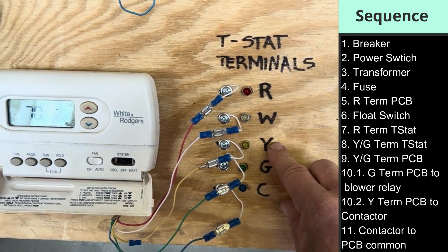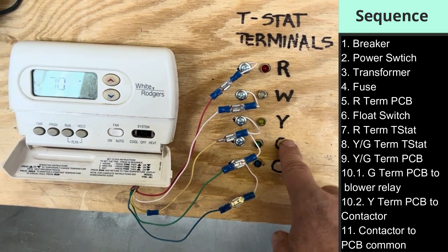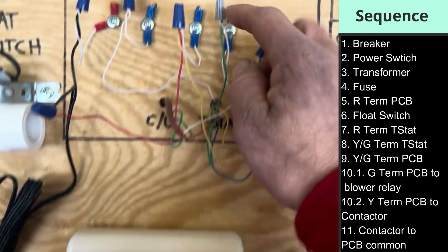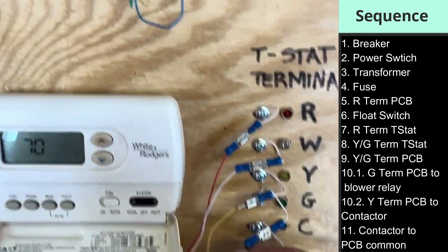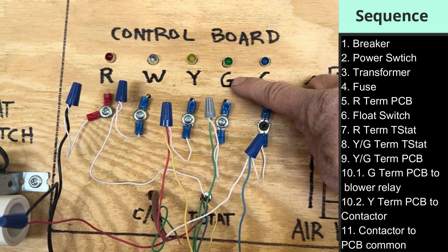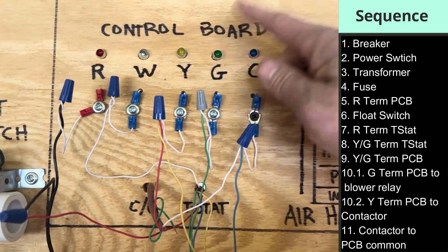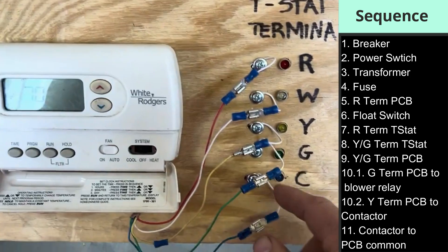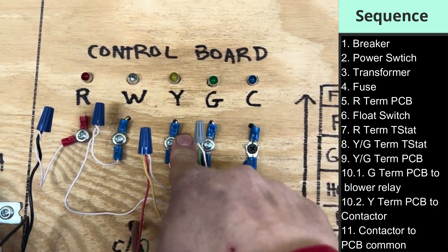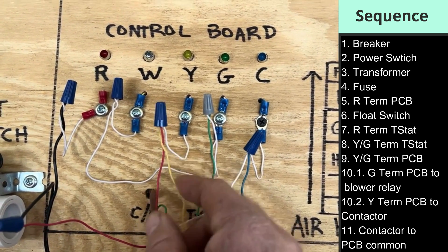In cooling mode, the thermostat makes connections between the R terminal and sends 24 volts to our Y terminal, and also sends 24 volts from R to G — Y is for cooling, G is for our blower motor. Both of these terminals get powered at the same time in cooling mode. The Y goes back on a yellow wire to the control board Y terminal, and G on a green wire back to the control board G terminal. Not every system has a printed circuit board with a Y terminal — sometimes you have a fan relay board — but either way the 24 volts from Y will connect to the Y terminal on the control board or pass through to the contactor on the outdoor unit.